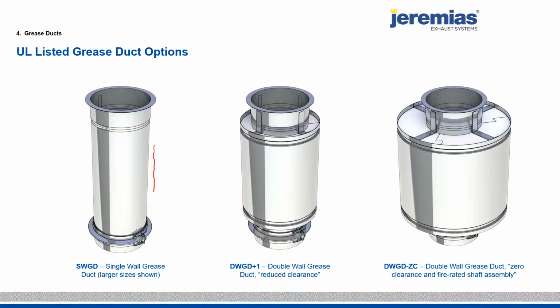You can use a reduced clearance option, which our system has a 1.25 inch thick fiber, which gives you a 2, 3, 4 inch clearance to combustibles based upon the diameter. This is typically used on single story restaurants, buildings, or maybe fast food restaurants. And then the third option is the zero clearance and fire rated shaft assembly. Our model has 3.25 inches. Other models on the market have 3, some have 4, but it's always between that 3 and 4 inch range for the zero clearance fire rated assembly.